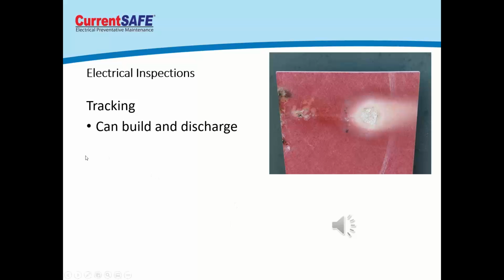So here's a great example of one of the inspections that I performed and we found at a facility I was working at. You can see on the screen here, this is part of the insulative board between medium voltage phases and some medium voltage switching equipment. And we can see here where the electricity has eaten a path in the board from the white part. That's where the energized component was, and we could see where it was building up and discharging over to the board, and then the board tracked through it. And on the left-hand side is where it was actually arcing over to ground. So you can see it just made a complete path there from right to left.